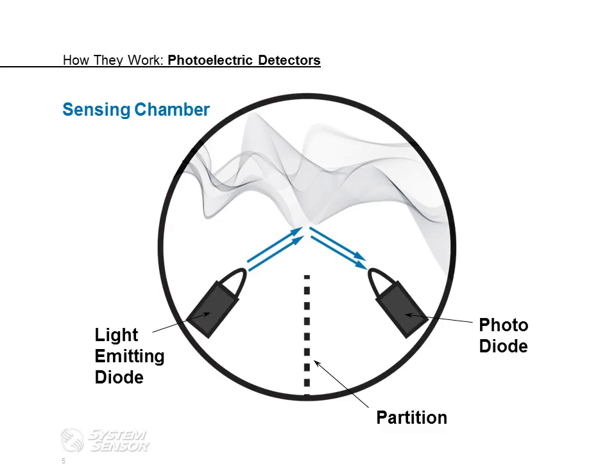The first technology we're going to talk about is the photoelectric detector. The photoelectric detector has really become the industry standard. The way it works, it uses a light-emitting diode and a photodiode, basically a transmitter and receiver. It sends a pulse of light into the smoke-sensing chamber that's dark in color, and then as smoke particles enter that chamber, that pulse of light reflects off of the smoke particles from the transmitter into the receiver, which causes your alarm.